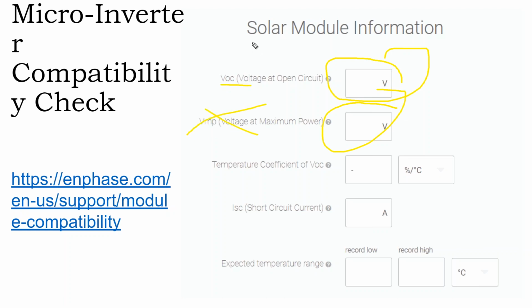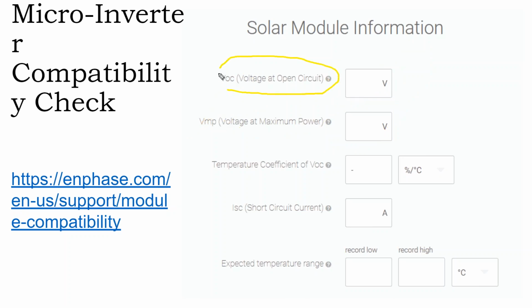Primarily, the open circuit voltage is more important, more of a design constraint than the operating voltage. The open circuit voltage, they're going to check to make sure you're not exceeding electric code. On a string inverter, that might be 600 volts. On a microinverter, it's all AC, so it's more just, is the module voltage going to explode the internal circuitry of the microinverter or not?